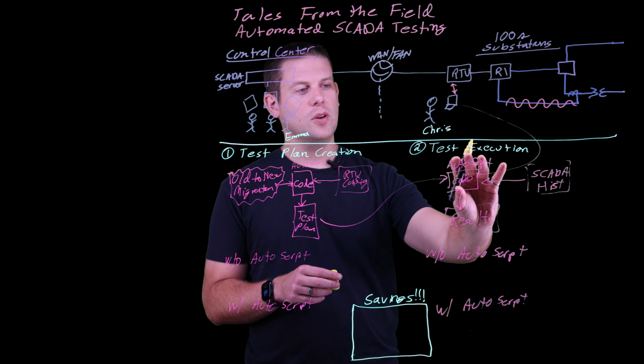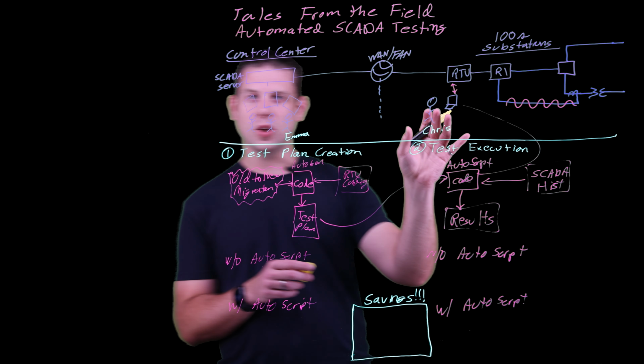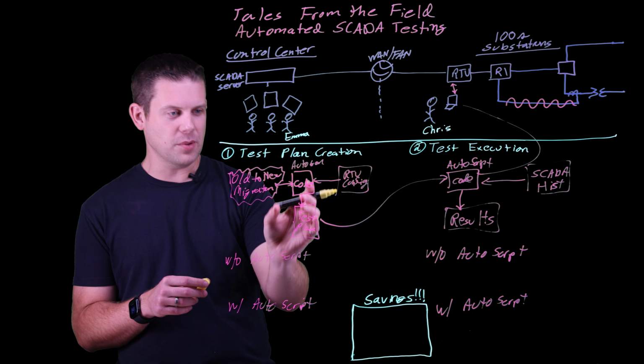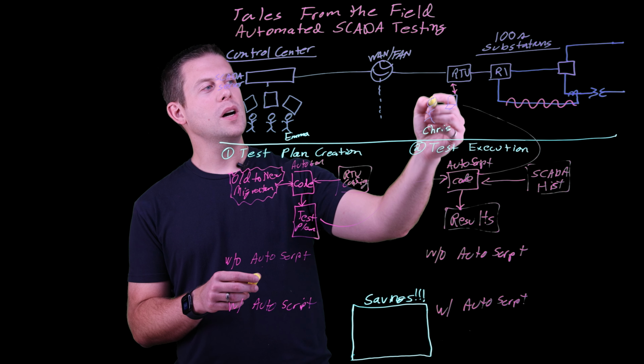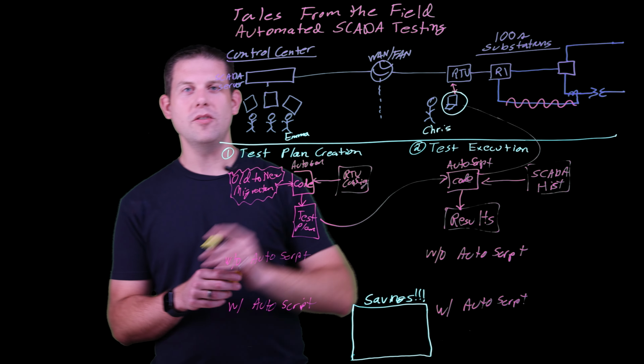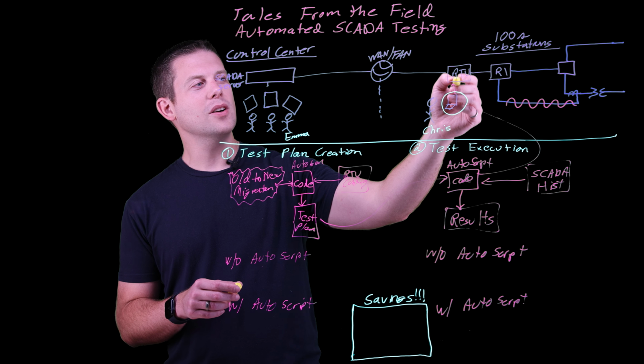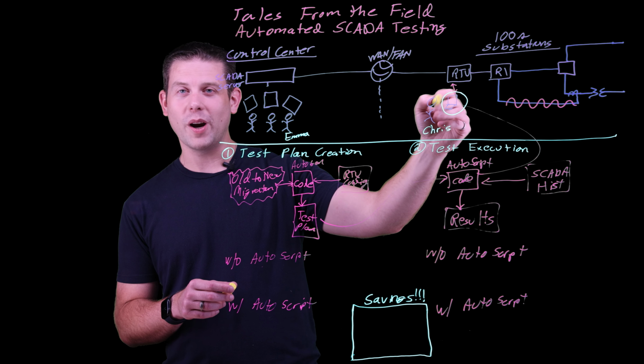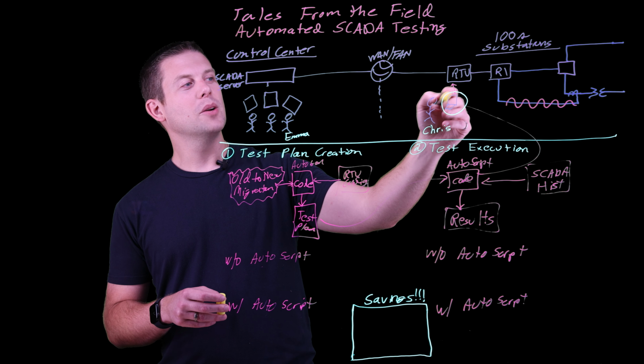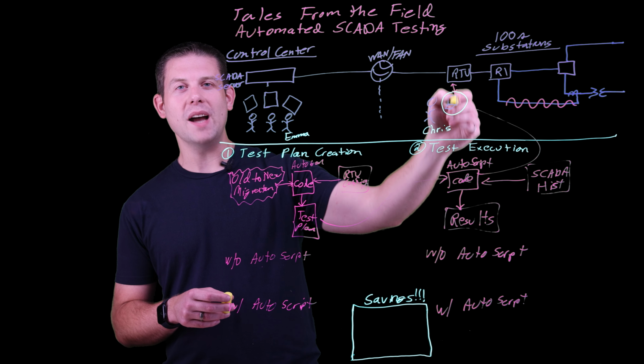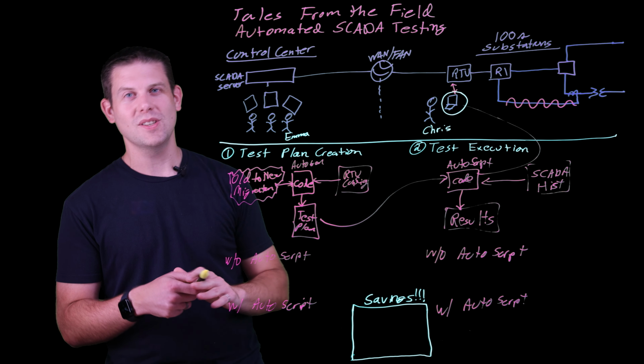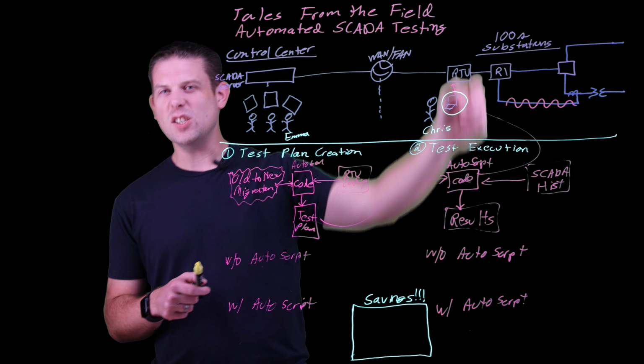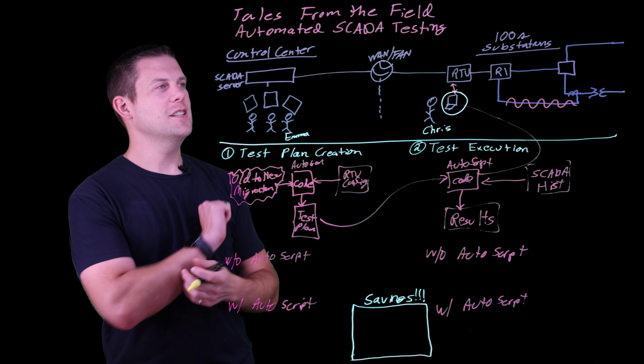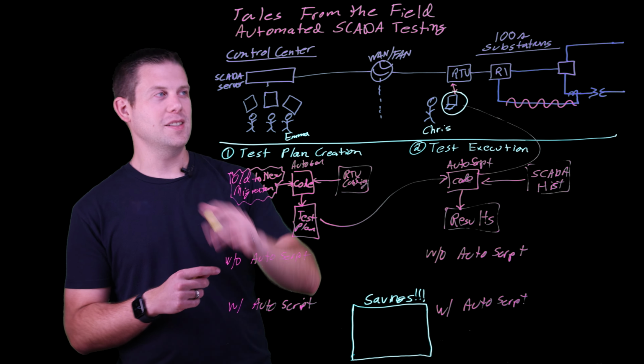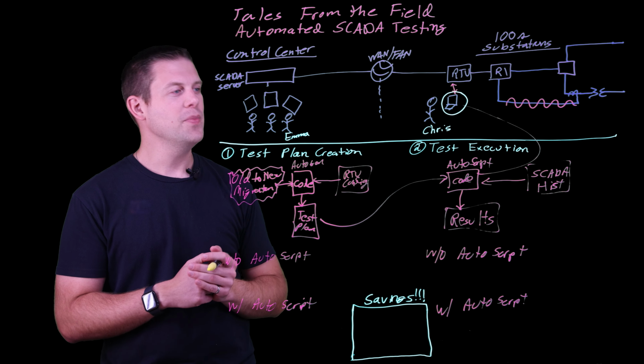We also created an actual test execution script able to take that test plan, run on a laptop in the field, hook into the RTU, and talk bidirectionally with it. Of course, for this type of testing, all the test switches are open so we can safely simulate an operation to the RTU.